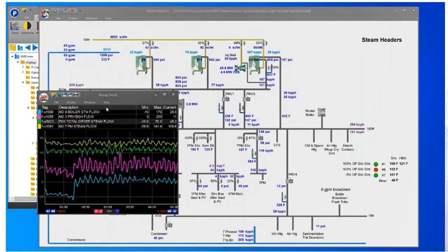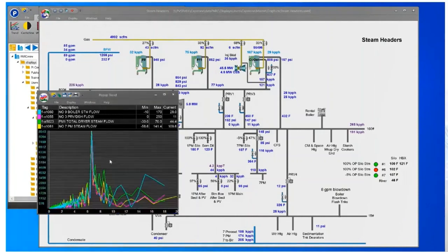So what we're going to do is go over to those 4, and we're going to go up to our FFT tool as a final check, and it's going to show us what the frequency is of each one of those tags. So you can see all 4 tags on there now, all 4 colors, and they all peak at exactly the same frequency. So we were right to chase it down to there and then back up, at least in the middle, that they're all being caused by one thing, and most likely, whether or not we can do anything with the tuning on that, at least that's the place where we'll attack the problem.